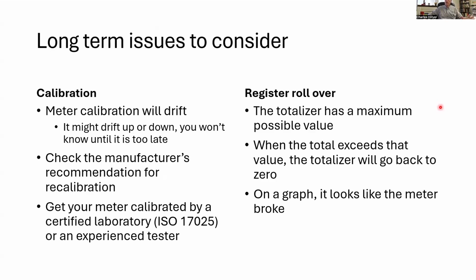And so on a graph, it's going to look like the meter broke, but it didn't. Now, this isn't something that's going to happen every year. It can take many, many years, especially if the newer meters can hold a very, very large value. But if you've got an older meter or older telemetry, and you notice that the totalized flow suddenly drops down to zero, that doesn't necessarily mean the meter's broken. It could mean that the totalizer has rolled over. But it's scary to see if you're not expecting it.